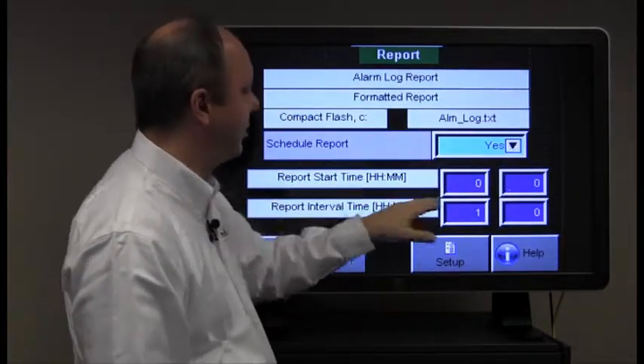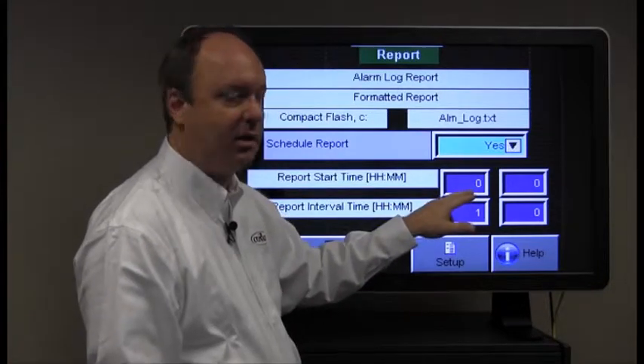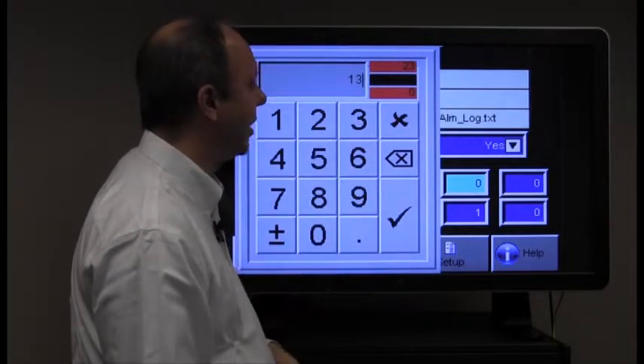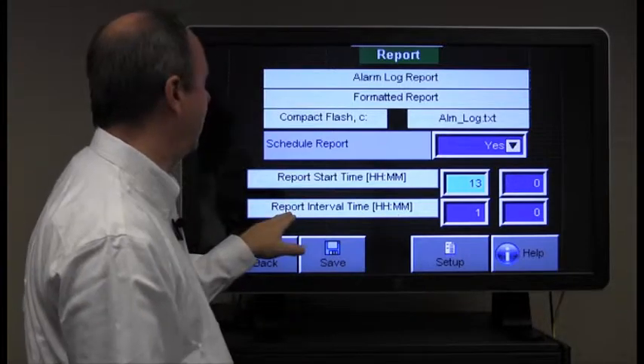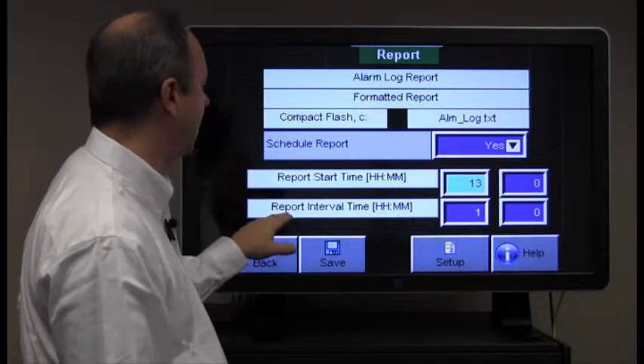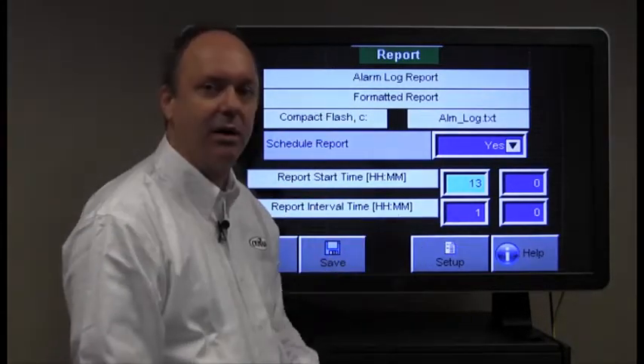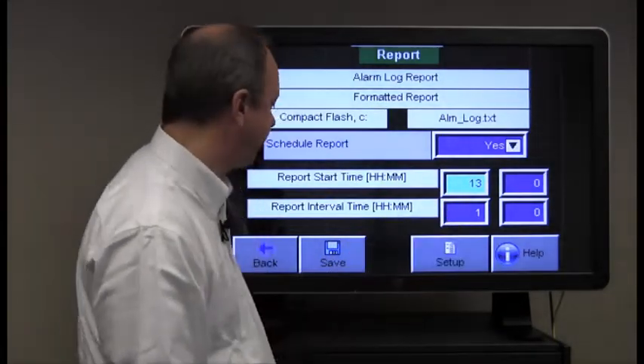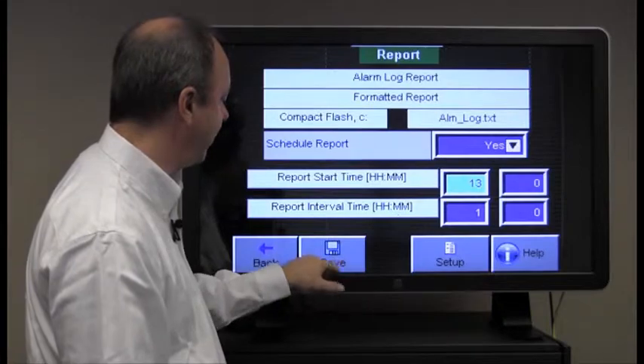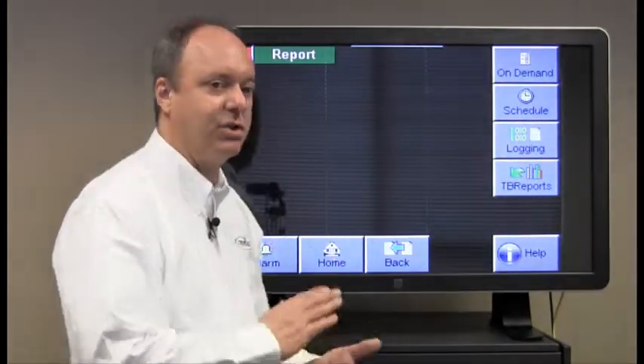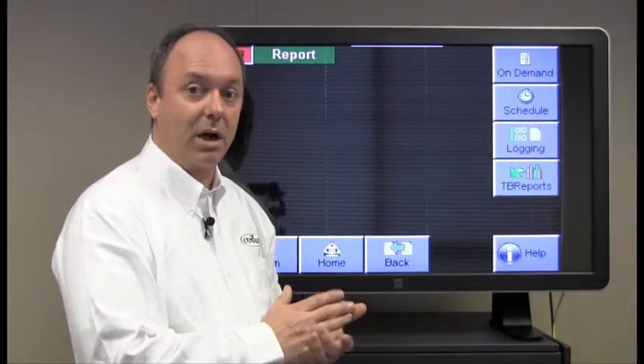The report start time in this particular case is set to midnight. If you wanted that to be 1 p.m. for instance, then you would set that to 1300 hours. It's based on a 24 hour clock. And you want this alarm report to occur on an interval of every hour, which again you could change to whatever interval you'd like.